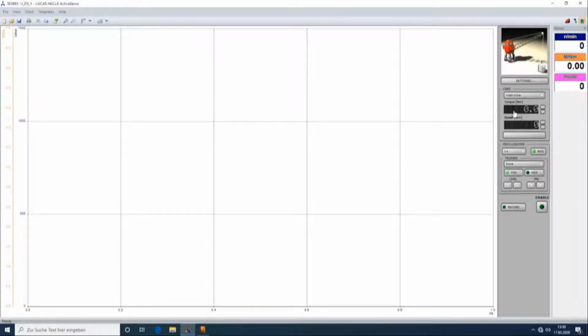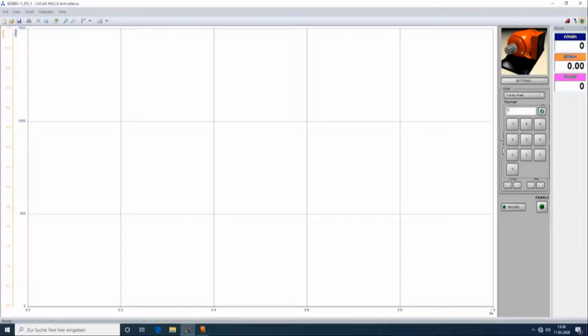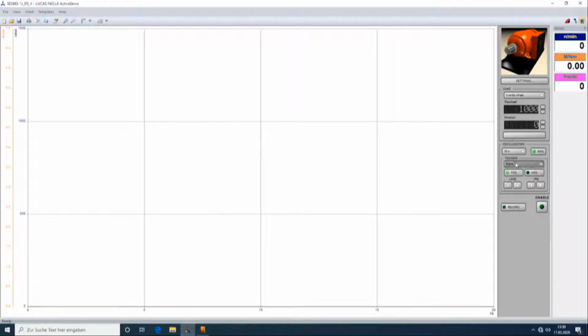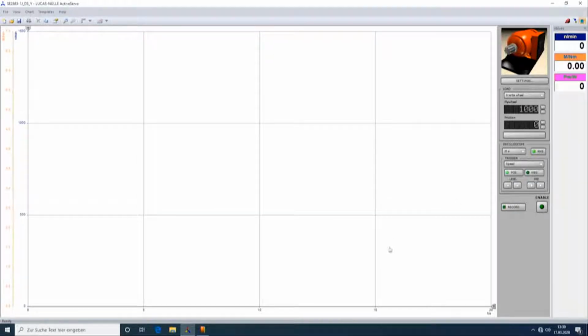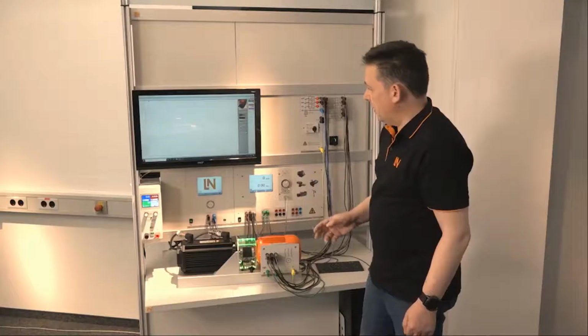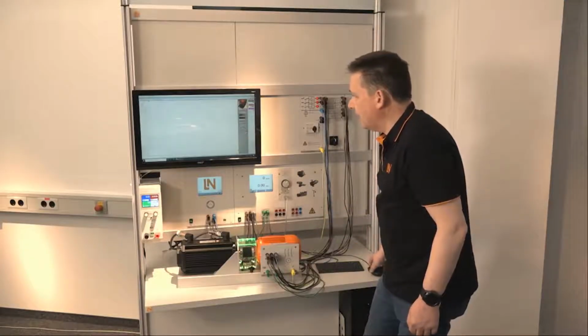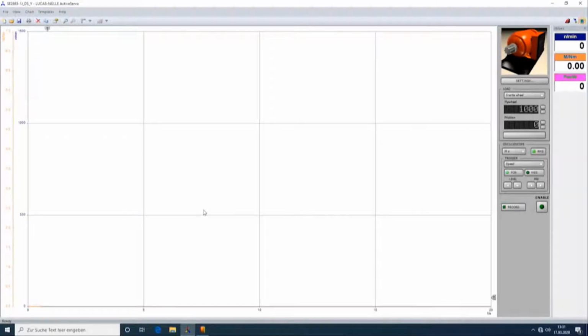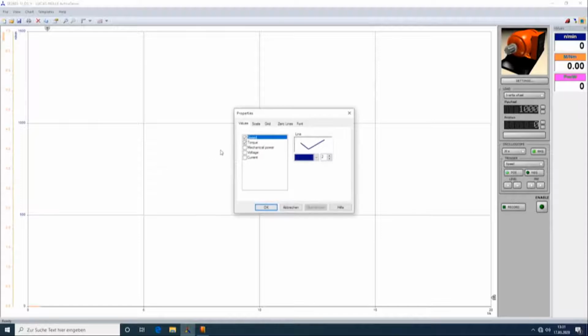To discover the inrush current, I will choose another working machine. I choose the inertia wheel, and then I change the flywheel to 1000 kilogram square centimeters. And now I can also adjust the axis for this. I will choose 20 seconds. For the trigger, I can choose the speed, for example, and here with these small anchors, I can select the triggering point. So now I have adjusted the flywheel with the values. But for the inrush current, it's also interesting to see the current. With a double click, I can adjust the current here.